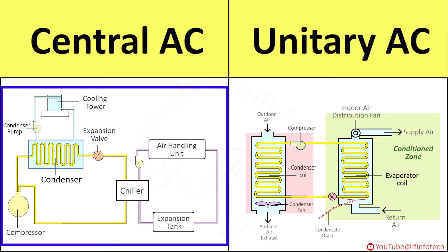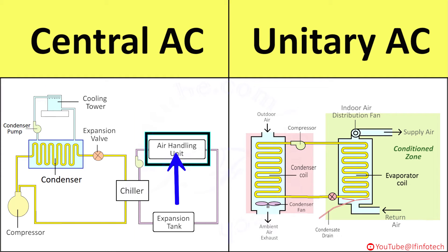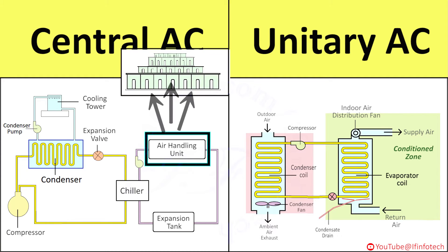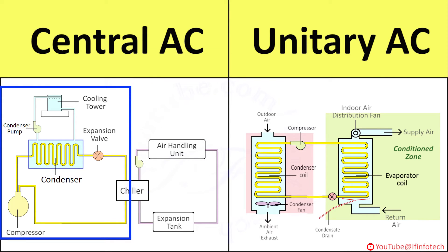We start with Central AC. In Central AC, all components are grouped together at a central control room where air is processed and distributed through ducts to various rooms in buildings. All rooms in buildings are air conditioned by the central air conditioning plant. The control room may be located in the basement of the building. Central AC is generally used for capacity more than 40 tons of refrigeration.